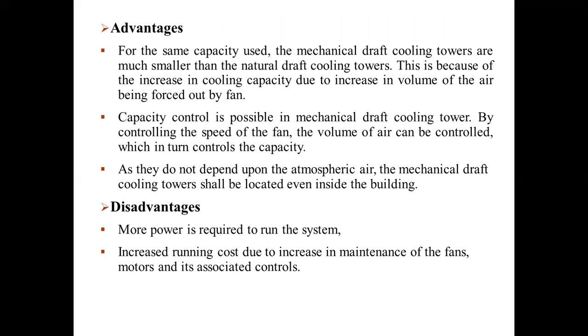The advantage is that for the same capacity, mechanical draft cooling towers are much smaller than natural draft cooling towers. This is because of the increase in cooling capacity due to the increase in volume of air being forced out by the fan. Capacity control is possible in mechanical draft cooling towers. By controlling the speed of the fan, the volume of air can be controlled easily, which in turn controls the capacity. As they do not depend on atmospheric pressure, mechanical draft cooling towers can be located even inside a building.